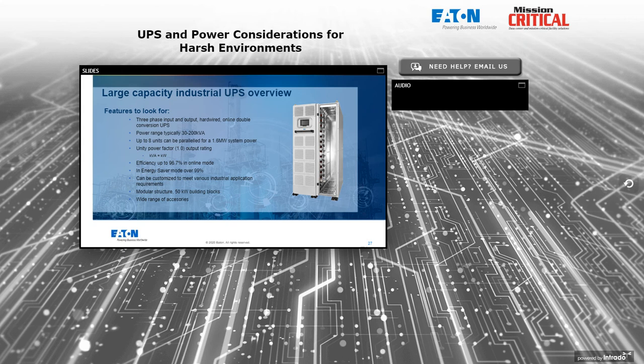Efficiencies in these type of products get up above 97%. If they have an energy saver mode, then they can exceed 99% efficiency, which means very, very little heat loss from the UPS. So it's going to be easier on the air conditioning system, or the UPS is going to be less likely to overheat its own environment. Remember, we still want to keep these UPSs below 50 degrees C, assuming they're rated even that high.